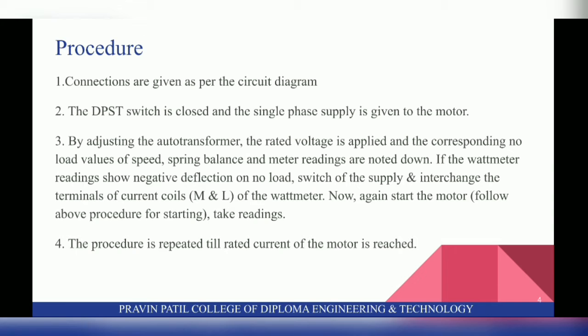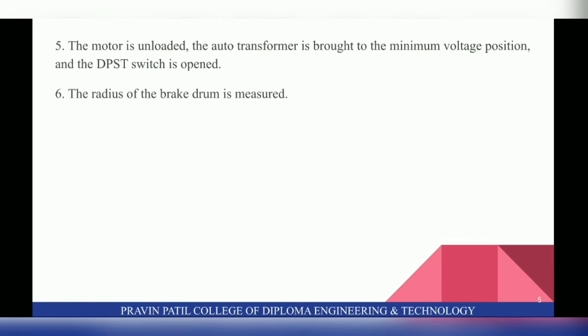If the wattmeter readings show negative deflection on no load, switch off the supply and interchange the terminals of current coils, that is M and L of the wattmeter. Now again start the motor and take the readings. Fourth is the procedure is repeated till rated current of the motor is reached. The motor is unloaded, the auto transformer is brought to the minimum voltage position and the DPST switch is open. The radius of the brake drum is measured. So this is the procedure for this load test on single phase induction motor.